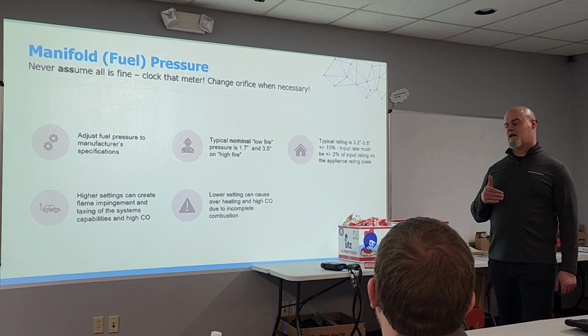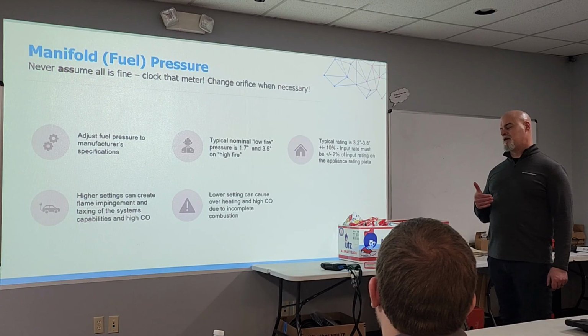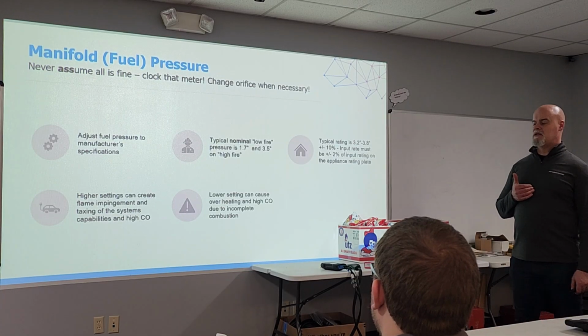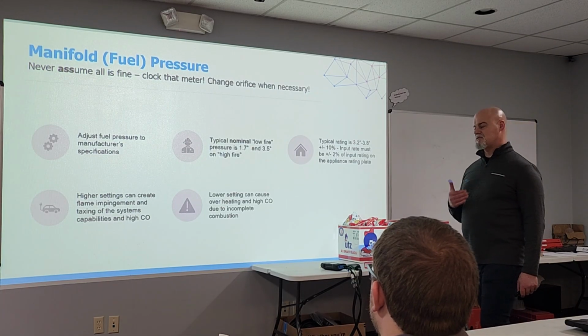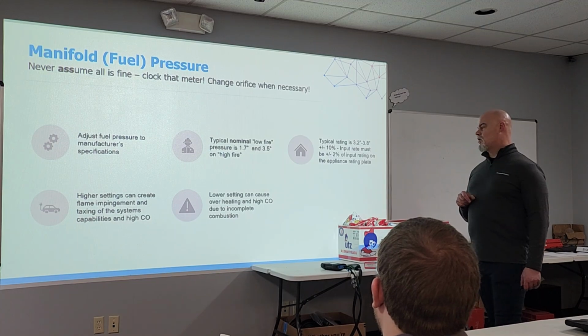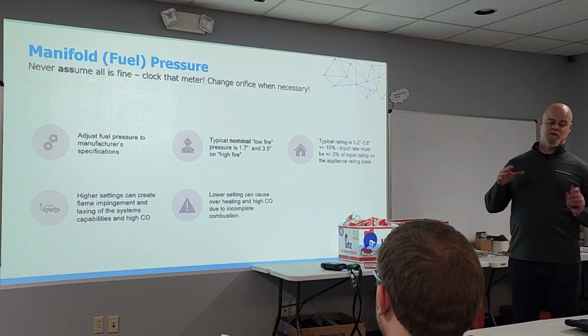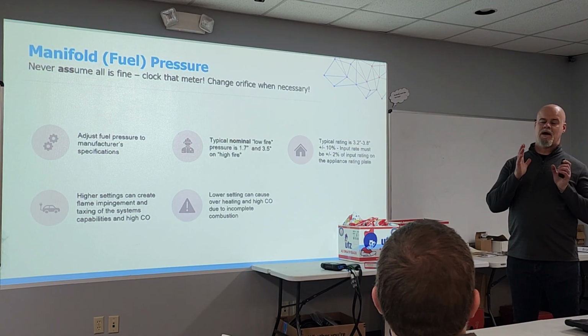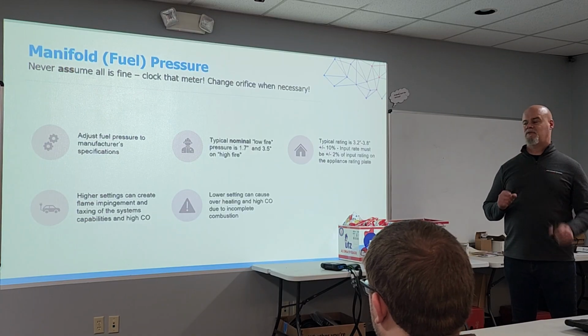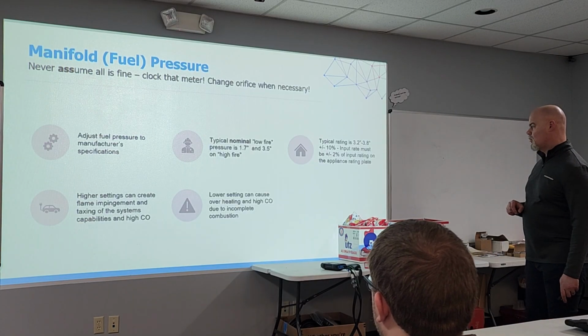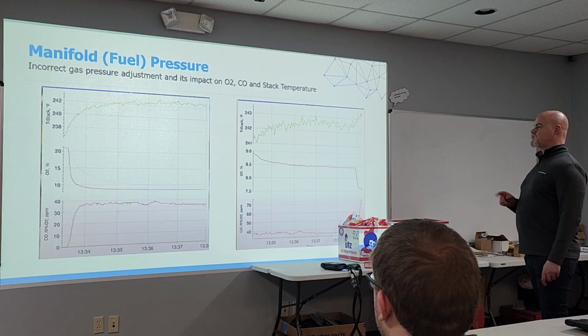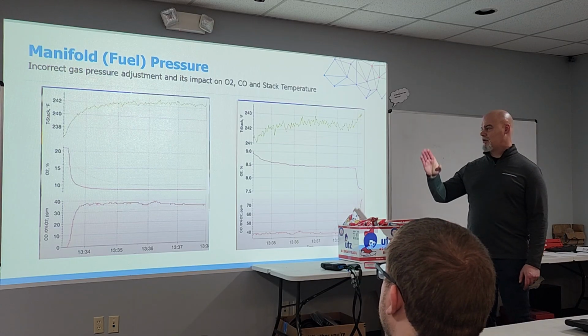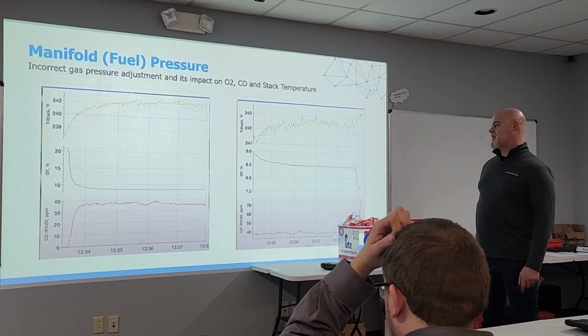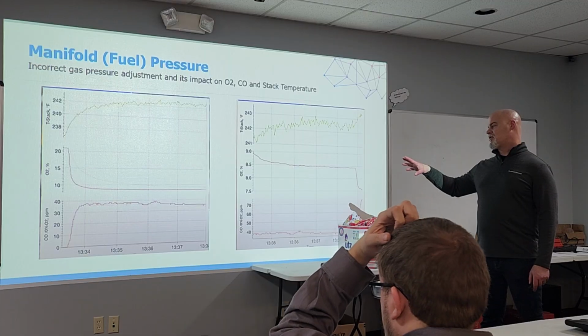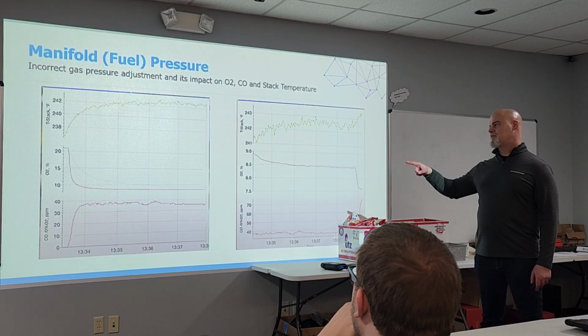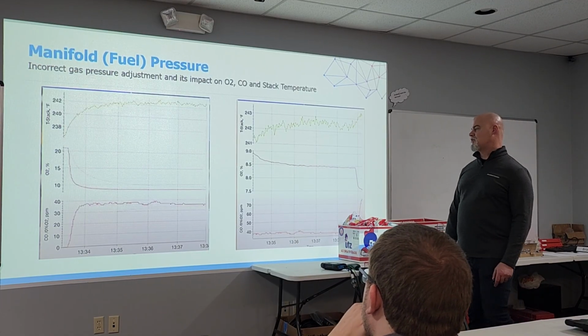Higher settings can create overfiring conditions, flame impingement, and taxing the system's capabilities, and also high levels of CO. As in low settings, can also create overheating and high CO due to incomplete combustion where we have that wider, incorrectly patterned flame. That's an issue, okay? What does this look like? It looks like this. Manifold pressure, an example. On the left is a before, on the right is an after. On the left, we have CO about 35 ppm, oxygen at about 9%, stack temperature about 243.